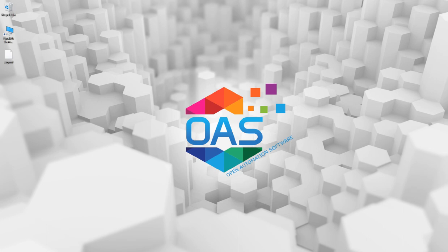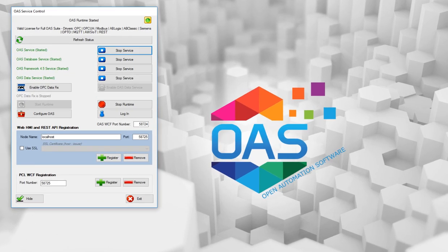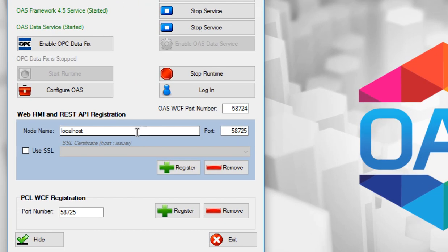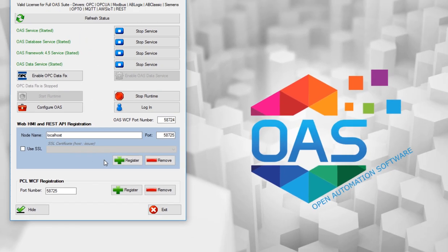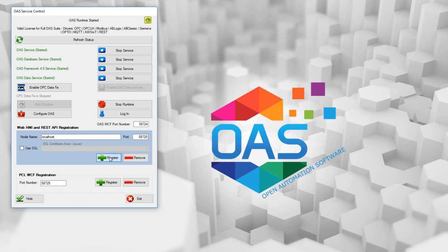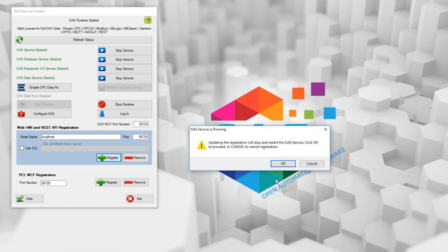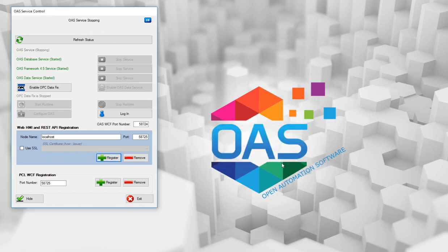So the first step is to open up the service control application, and under the Web HMI and REST API registration section, you're going to select the port number that you want to run this on. If you want to use SSL, you can check off use SSL, and you'll have to have a certificate installed on the server to support SSL. So click register and it'll stop the services. And once it's complete, it'll start the services back up again and you'll be all set.